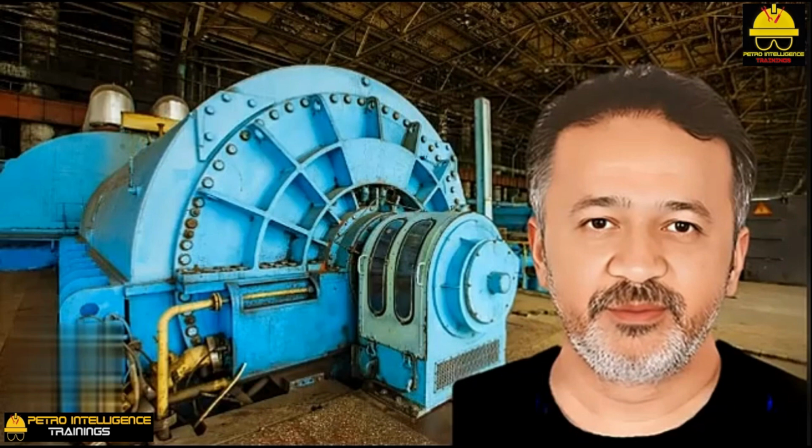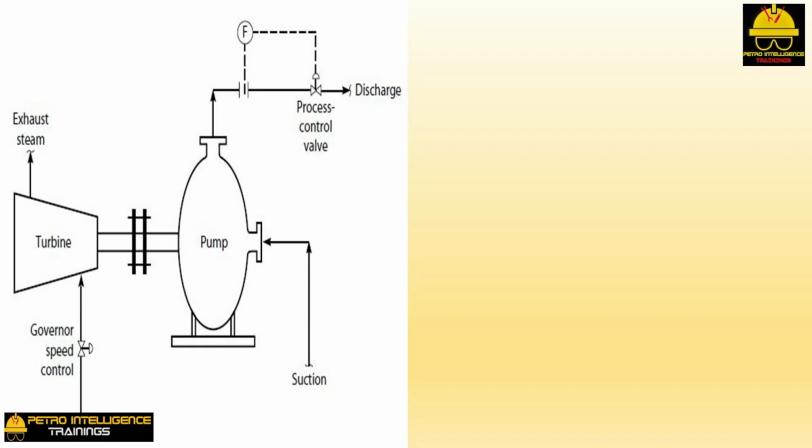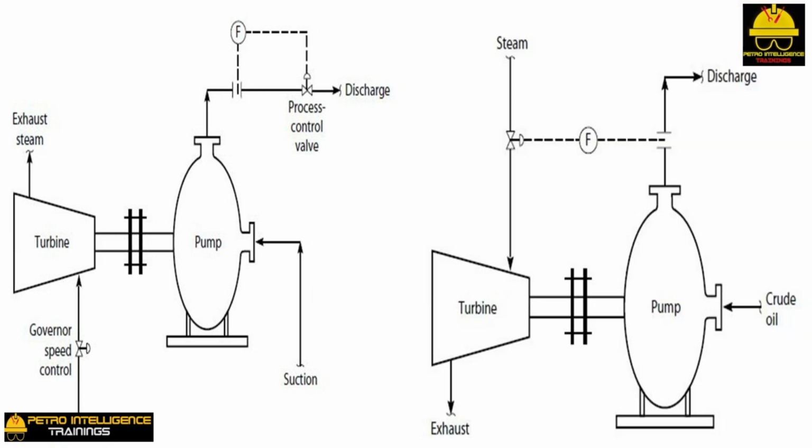An old, but better, idea. The control scheme shown in the picture is certainly quite common. But is it the best? This picture is a copy of the crude charge system in a now-defunct refinery. It worked fine. The required flow of crude directly controls the governor.